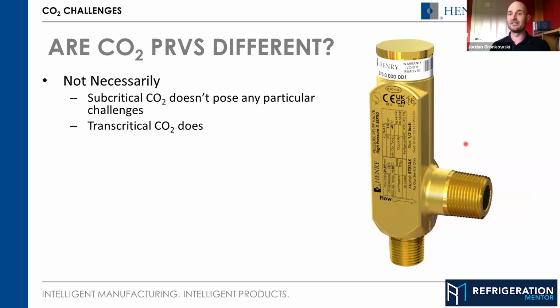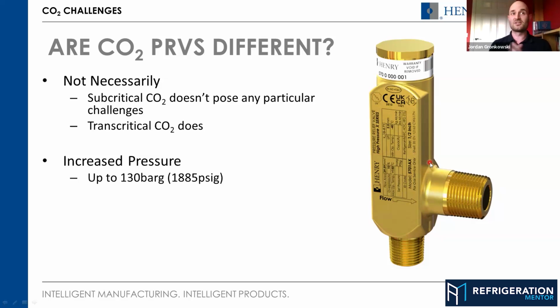Subcritical CO2 doesn't really behave any massively different from any conventional refrigerant. So although we at Henry have a high pressure range of valves specifically designed for CO2, all of our valves, even our low pressure ones, are suitable for CO2, because at your subcritical, low pressure end, the normal valves work fine. But transcritical has its unique challenges. The obvious one is increased pressure. I've put here 130 bar because that's where our limit is on our pressure relief valve range, but I've heard up to 150, 160 bar in some systems.